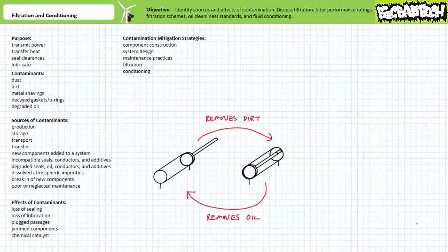Well-designed systems minimize inefficiencies that can contribute to excess heating of the oil. Excess or prolonged periods of heat can actually damage the molecular structure of oil such that the oil itself becomes a contaminant forming weak acids or soaps. Heat damaged oil exhibits different lubricity characteristics and viscosity and pH levels than regular oil and can weaken and pit surfaces and coat parts and plug ports. The resinous byproduct of heat degraded oil form a sticky sludge known as a varnish that can coat passageways, plug ports, and glue ordinary moving parts together. For this reason, systems take care to avoid scenarios that generate excess heat. For example, prolonged actuation of the pressure relief valve can be avoided by a system that minimizes stall time of the actuator or makes use of tandem or open center valves. Better yet, simply stops pumping during idle periods.